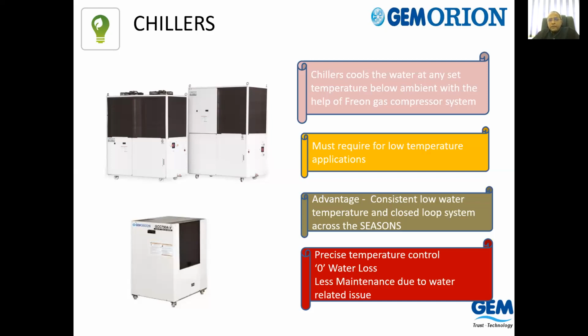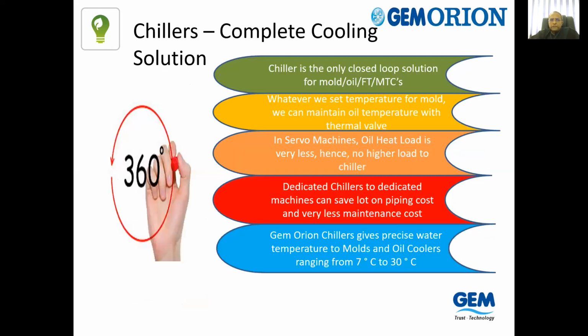And another advantage is that even for your hydraulic power pack system, because the cooling is done by the same water at say 7 to 14 or 15 degrees, or whatever your mold cooling temperature is, your hydraulic power pack also is maintained constantly at whatever set temperature by using a thermostat throughout the year. So that will ensure the life of the hydraulic components and all are maintained very reliably, plus the life of the equipment, life of your mold, life of your power pack, heat exchanger, your internal systems are all well protected because of that.